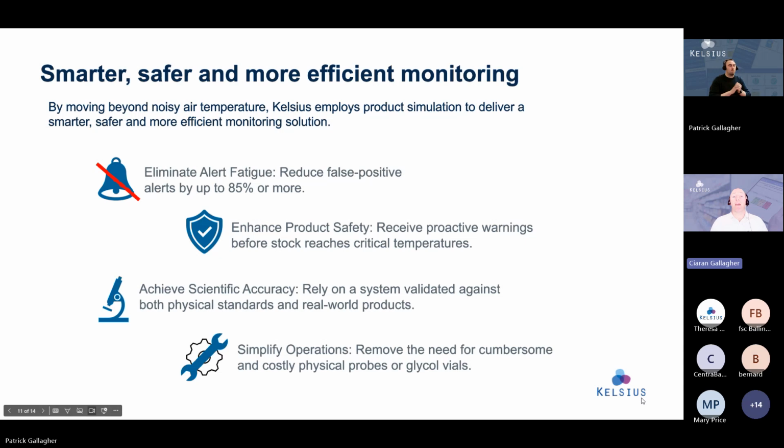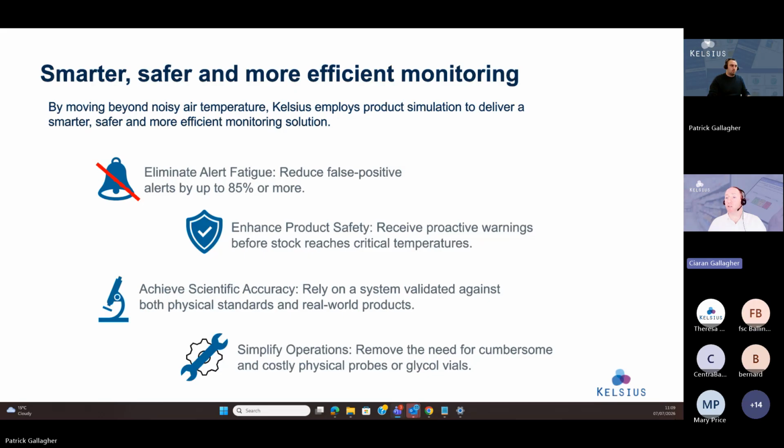So the findings that we found from deploying this with our customers. The first one is a massive reduction in false positive alerts, because we're setting them up against product as opposed to air temperature. We have been able to reduce that by as much as 85% in some scenarios. Because we've been able to do that, it's enhancing the product safety of the stock or samples that you have under your management. The knock-on effects of that are that you're making your customers safer, you're making your patients safer by doing so.